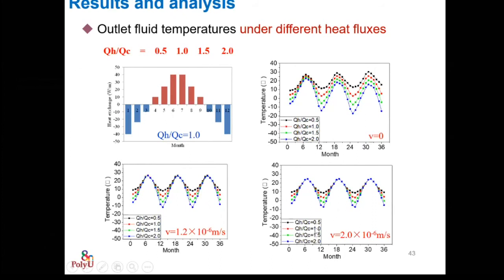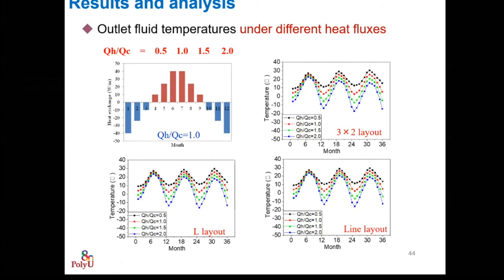For different ratios of the heating and cooling load, generally speaking we need a balance, that is QH over QC should be equal to one. That means the amount of energy injected into the ground should be equal or similar to the amount extracted from the ground in winter, so that we have energy balance in the ground. Otherwise, the soil temperature in winter could be very low, and the soil temperature in summer could be very high, then the COP will be lower.